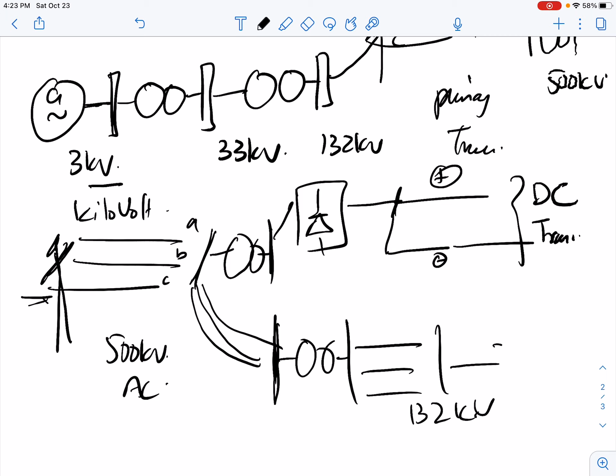At the delivery end, we step this down to 132 kV, then again to 33 kV using transformers, and finally we step this down to 11 kV with different feeders. We call this the transmission line feeder, and then distribution transformers step this down further to 415 volts line to line in Pakistan, and 230 volts line to neutral.